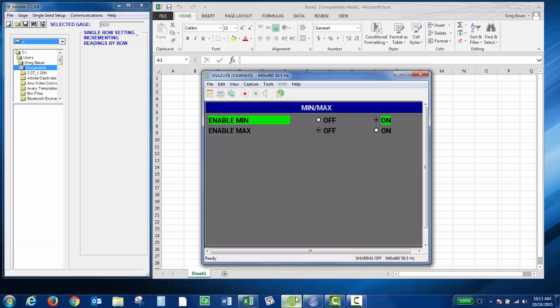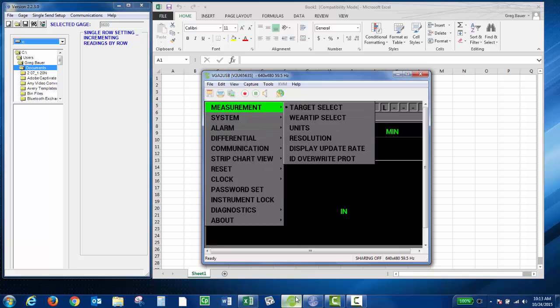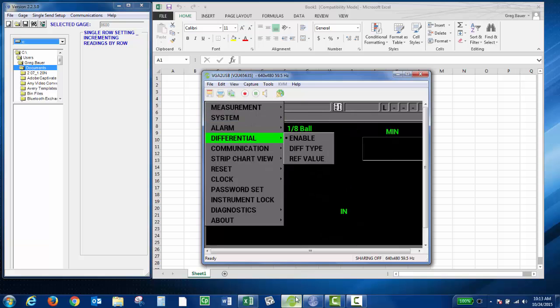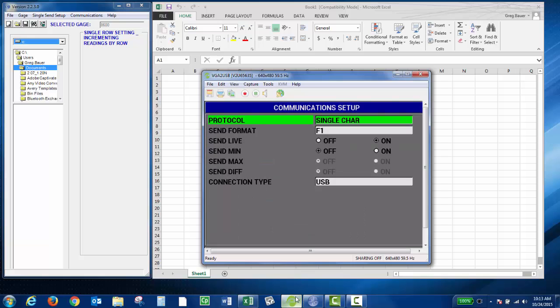Then you can press the measure key. In the top right, my min value will be captured, and then I have my live thickness right in the middle. Then you'd want to press the setup key and go into your communication settings. You do have to change the send format to F3.